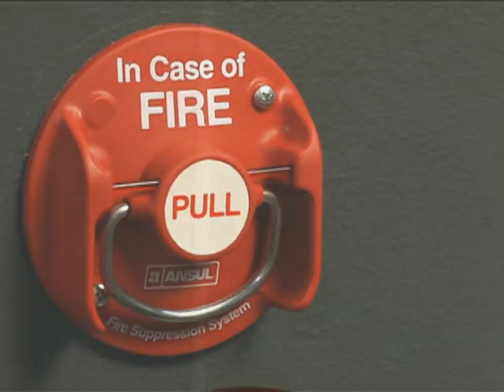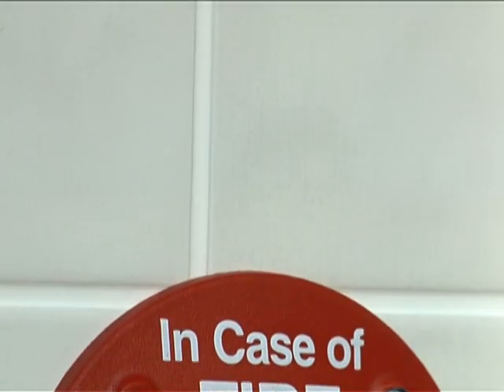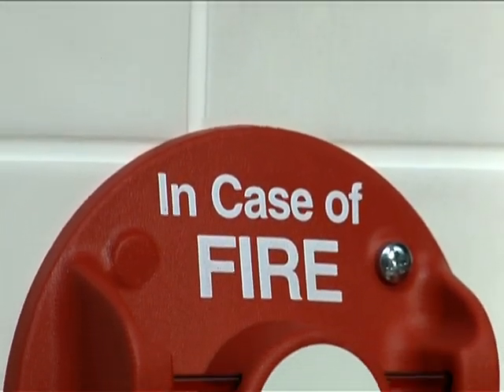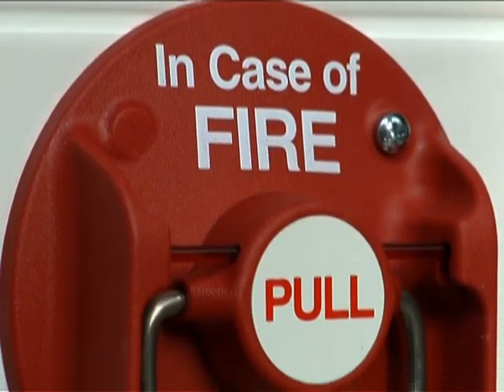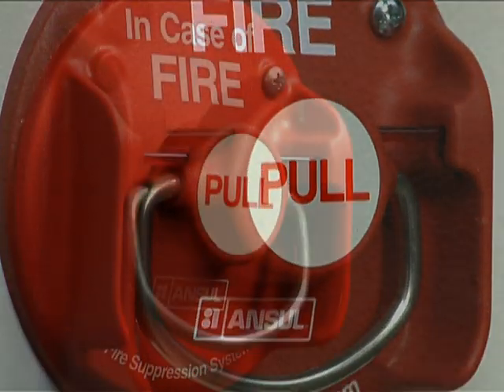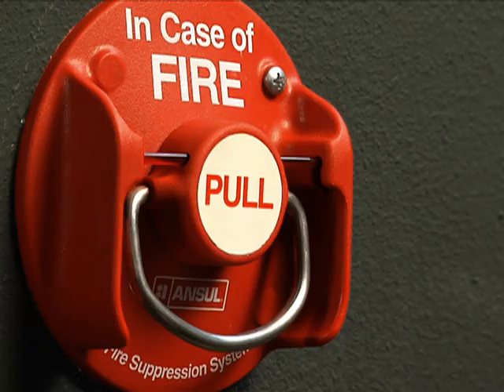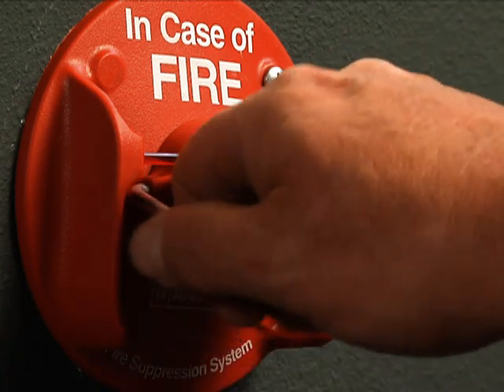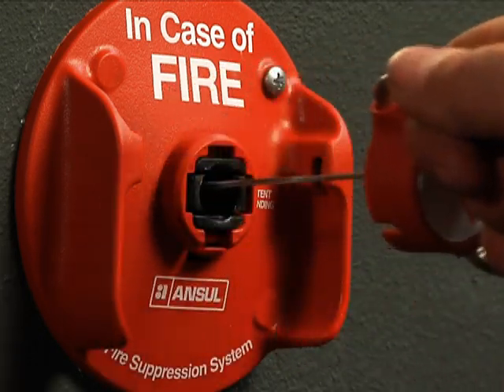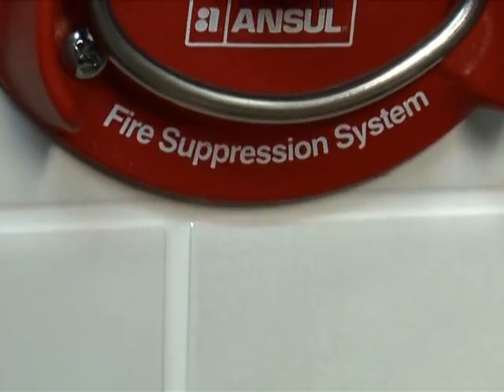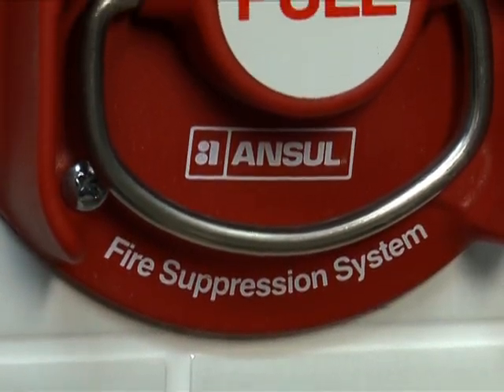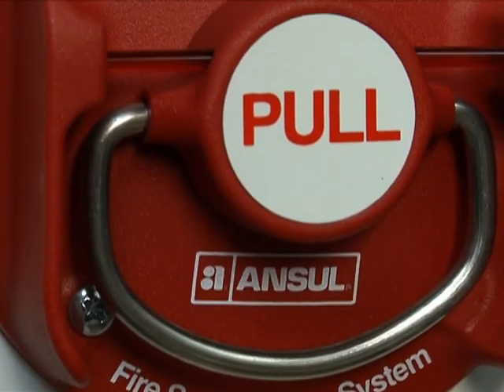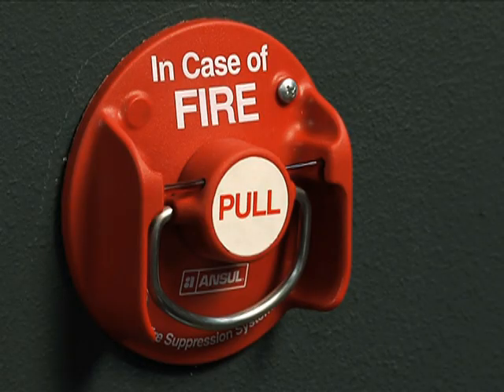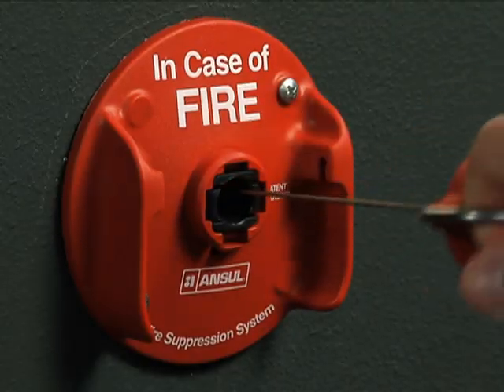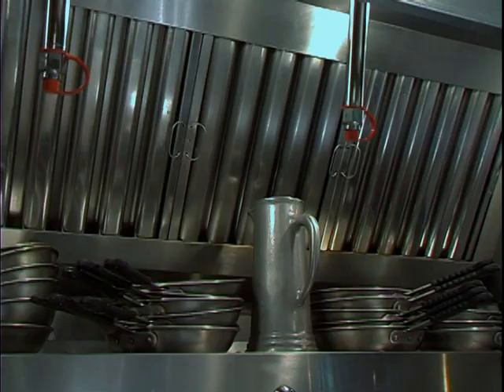In certain instances, it may be necessary to discharge the R-102 system manually. The new ANSUL remote manual pull station is made out of a tough red molded composite material, which makes the pull station more readily identifiable and easier to recognize as the manual means for fire suppression system operation. With a built-in guard to protect the pull handle, it is simpler, smarter, and easier to use than ever. It eliminates the need for an additional cage to be installed around the assembly and has an enlarged pull handle, allowing for easy three-finger operation.